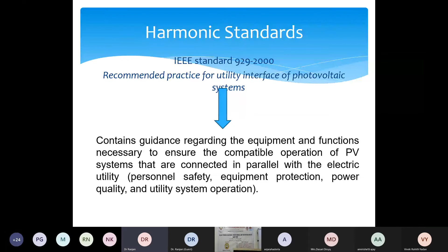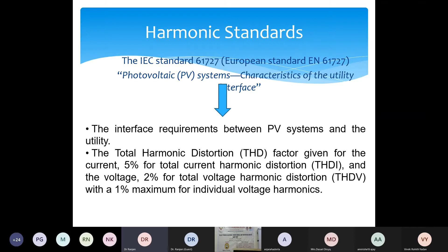And total harmonic distortion for the current should be 5% with total current harmonic distortion, and 2% for the voltage harmonic distortion, within a 1% maximum per individual voltage.